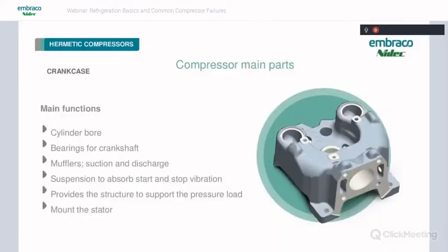So one of the items you might have seen in there was the crankcase. Its main function is it holds the cylinder bore, it holds the bearings for the crankshaft, the suction and discharge mufflers. It mounts the suspension to absorb start and stop vibrations, and it provides a structure to support the pressure load. And it also mounts the motor stator.